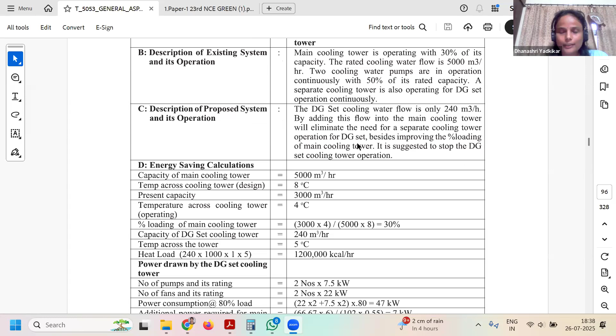So they have converted 240 meter cube per hour into 66.67 liters per second, multiplied by 6 and divided by 0.55. Here they haven't mentioned what is 0.55 and what is 102. So 0.55 is nothing but the efficiency. You are dividing this hydraulic power by efficiency so that you get the power which is required to make the flow of 240 meter cube per hour. This is the flow requirement of the cooling tower of the DG set. Okay. So this is coming to 7 kilowatts.